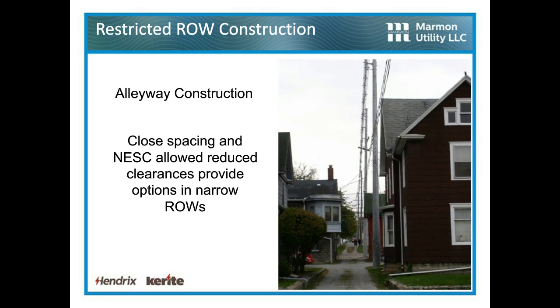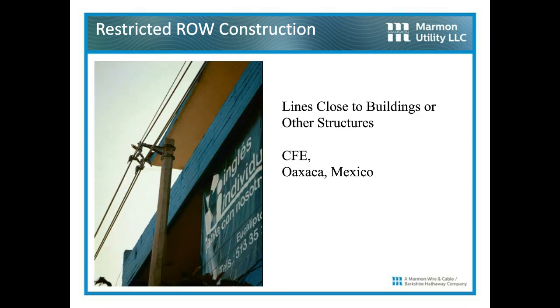Alleyway construction, again, this is a triple circuit substation exit going down a residential alley, just 2 or 3 blocks, and this is instead of going a half mile down the street, 2 or 3 blocks over and a half mile back, so they saved a fortune with this application. And we have a lot of these applications where we're close to the buildings. Do a lot of this in the U.S., downtown areas of a lot of munis and co-ops, and this happens to be in Mexico where they put a second story on this house, and it just was too darn close for bare wire. It was an accident waiting to happen, so that was converted to spacer cable.